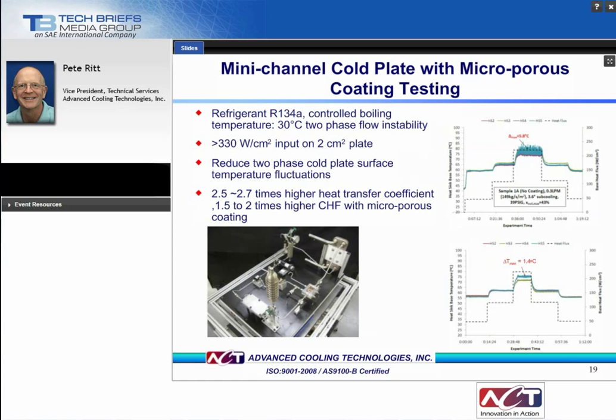Here are some results we can share with this approach. In the system, the refrigerant that was used was R134A. Boiling temperature was controlled to 30 degrees C. Heat input on the evaporator was 330 watts per centimeter squared across a 2 centimeter squared area. A picture of the system setup is seen on the lower left. Results can be seen on the right.